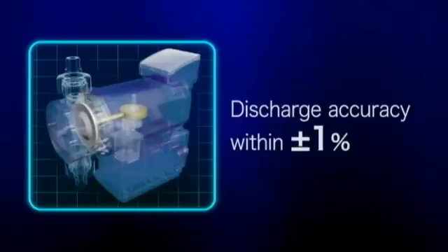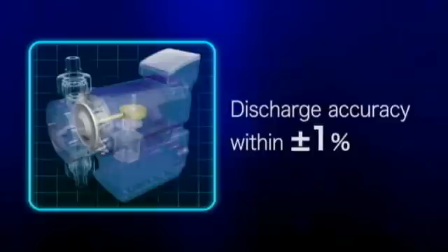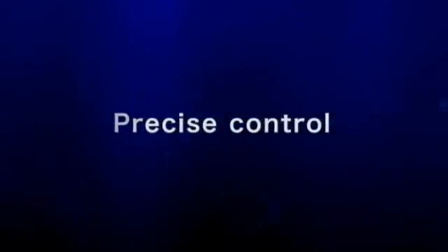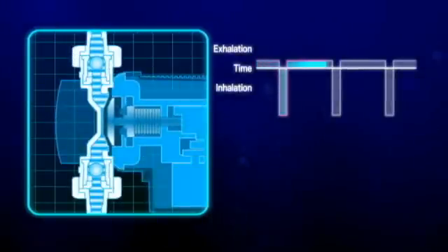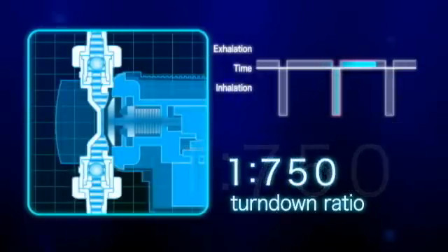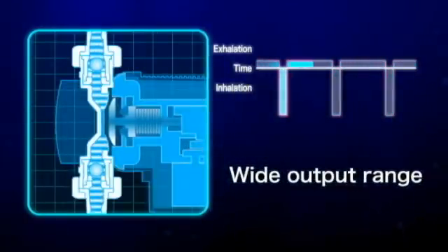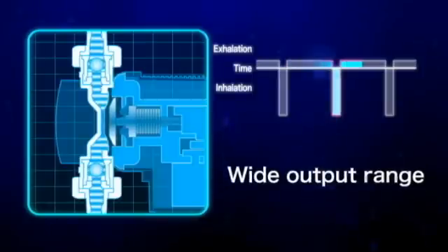Discharge accuracy within ±1%, regardless of the output. The IX maintains precise control of the suction and discharge stroke processes, resulting in accurate, consistent chemical feed. With a turn down ratio of 750 to 1, the IX series pumps can be utilized in a broad range of applications and flow rates. The pump controller utilizes several control methods for output control.